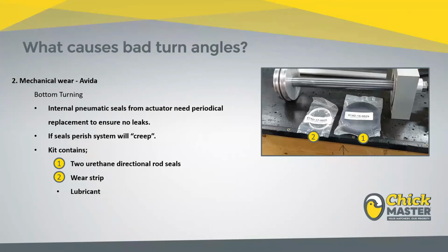Now, your mechanical wear on your bottom turning Avida is next to non-existent. The pneumatic actuator itself is pretty much maintenance free. The two main things you want to look out for, and this is once every 2 years or so, is your mechanical seals on the inside of that rod. And this is mainly an issue if you don't have a filter or a condensator on your compressor supply. And you also want to take that actuator apart and just re-lubricate it every now and again. Now, the lubricant that we use is something called Magna Lube, and it's a non-water-based lube for life, is what they call it. So in an ideal world, you put that in and you'd never need to touch it again.